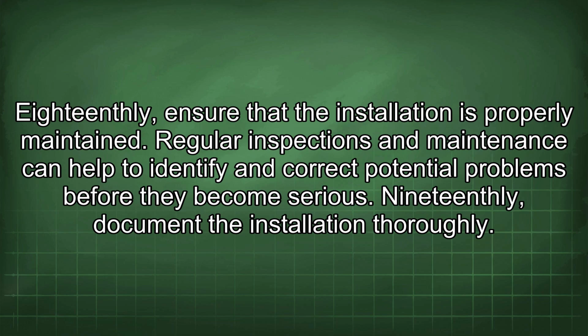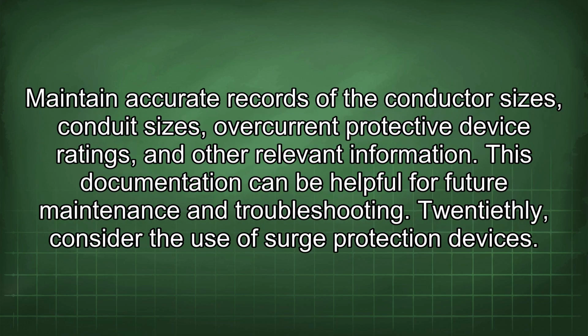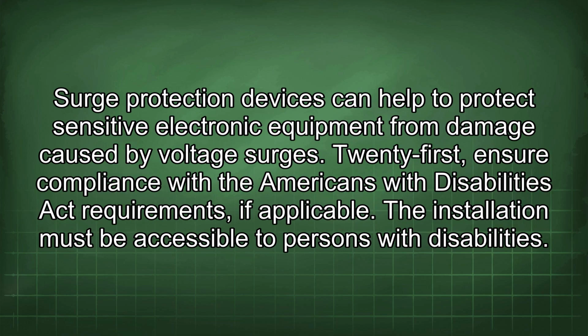19thly, document the installation thoroughly. Maintain accurate records of the conductor sizes, conduit sizes, overcurrent protective device ratings, and other relevant information. This documentation can be helpful for future maintenance and troubleshooting. 20thly, consider the use of surge protection devices. Surge protection devices can help to protect sensitive electronic equipment from damage caused by voltage surges.